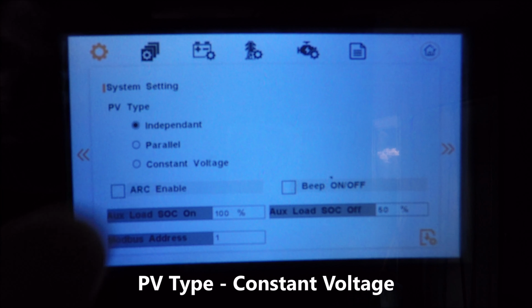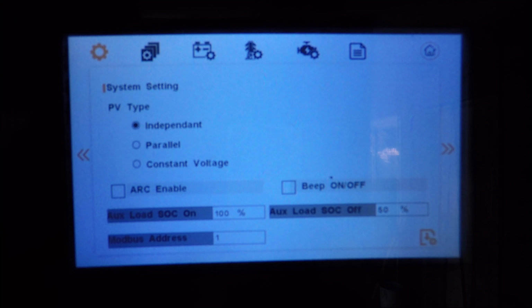If you select constant voltage, this will set a constant voltage across all the MPPTs using the lowest voltage produced. This disables all the dynamic functionality of an MPPT tracker, and it does not adjust for maximum power settings. It can be used in some very simple setups such as battery charging only, or some integration with other older systems, and running diagnostics if there's some problems that you are having to trace down on your array. In most use cases, constant voltage is not used.